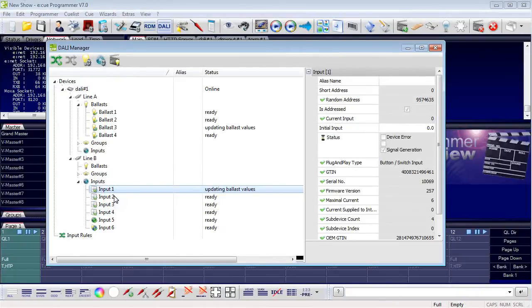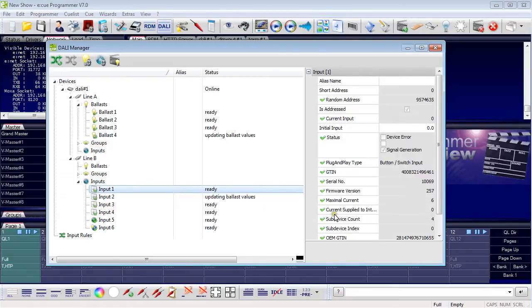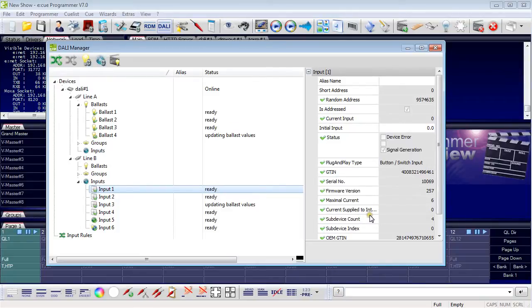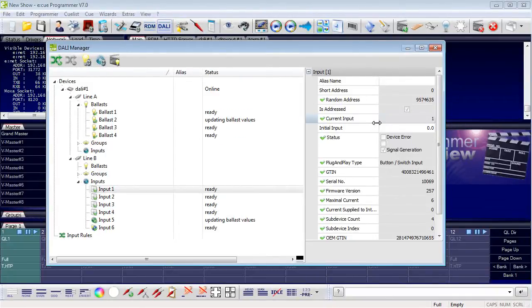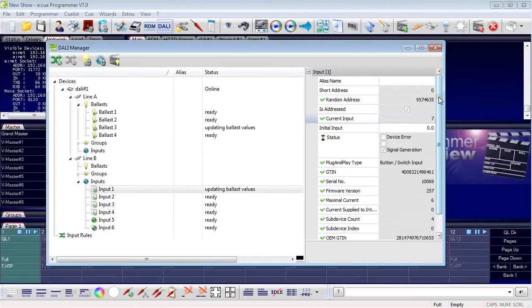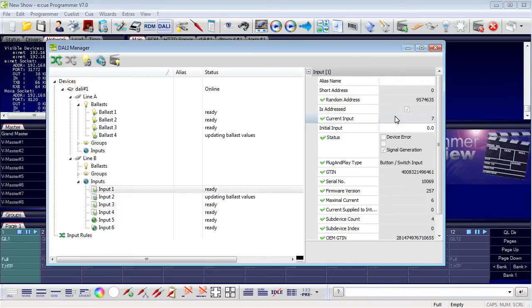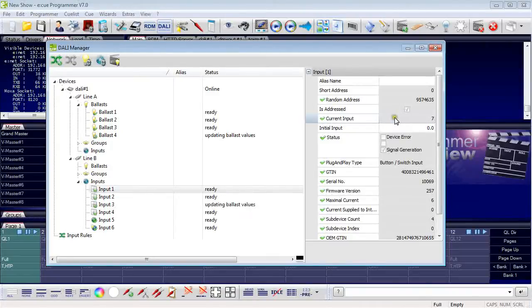Buttons are the most simple input devices, so there is not much to configure in the DALI manager. But you can see that pressing buttons will give different output values depending on how long you press the button. For example, button number 1 has a current input of 0. A short press gives a current input of 1, keeping it pressed gives a value of 4, and releasing gives a value of 7. The trigger engine will handle these two different types of use — short press or long press.